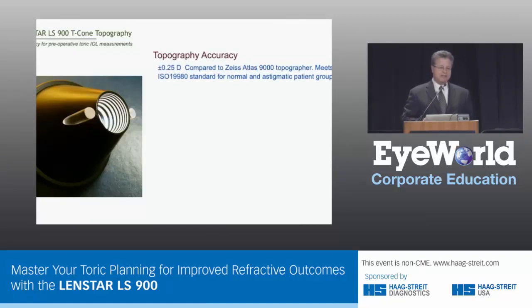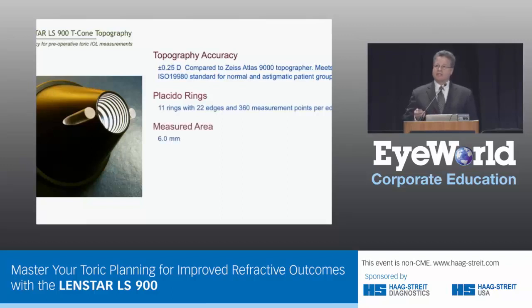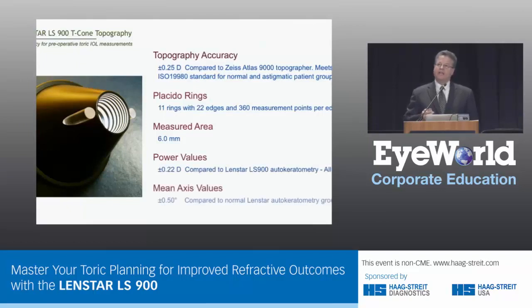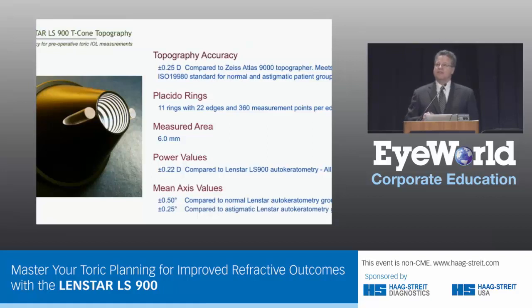This is what the T-cone looks like — it goes right on the front of the LENSTAR. We like to joke that this turns the LENSTAR into a Swiss Army knife: it doesn't have a toothpick and a spoon, but it has just about everything else. It looks just like the Zeiss Atlas topographer with the same sort of Placido rings. The measurement area is about 6 millimeters instead of 9 millimeters. It was validated against the Atlas 9000 topographer and came out almost exactly the same, both for normal spherical eyes and astigmatic eyes, and also validated against the LENSTAR Ks, which are, in my opinion, the best Ks in the business.